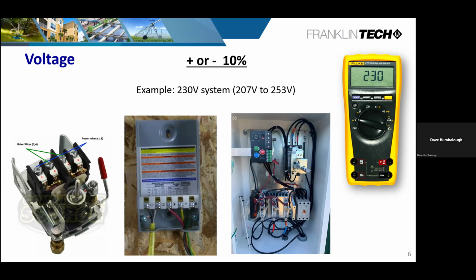Wire side, or I should say the wire threshold. Most of the stuff that's rolling in here in the United States and is produced here in the United States has a 600 volt rating. You'll have to be wary because there is a lot of offshore wire that comes in. Make sure and pay attention that it is still rated under the UL certification of 600 volts. What you'll typically see is some of the foreign wire coming in, because they're used to 50 hertz, carries a threshold of 500 volts.